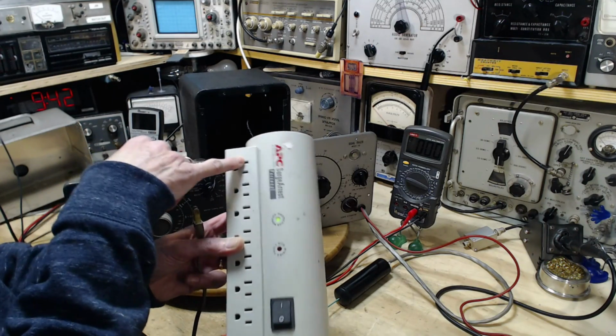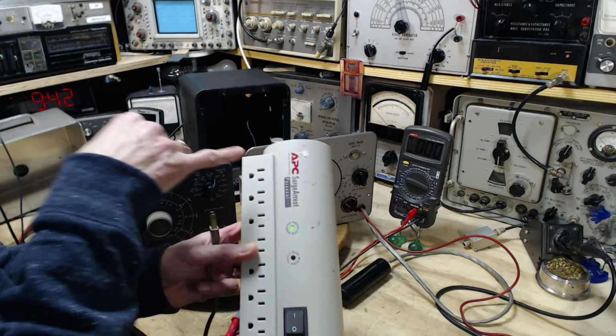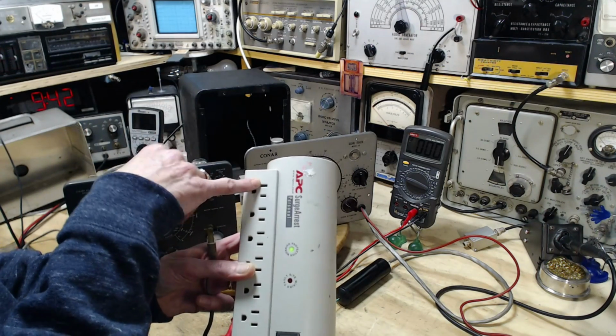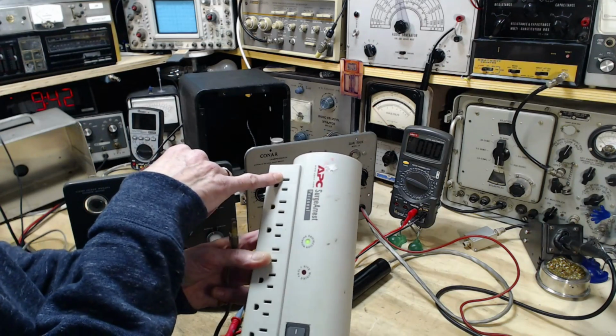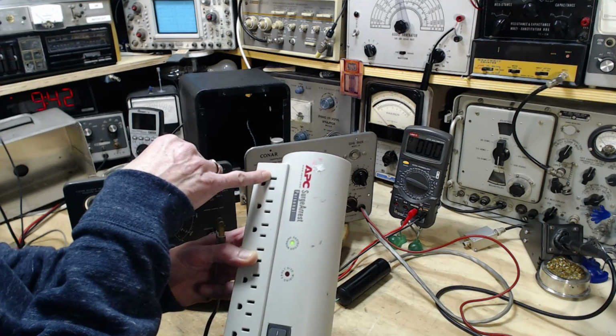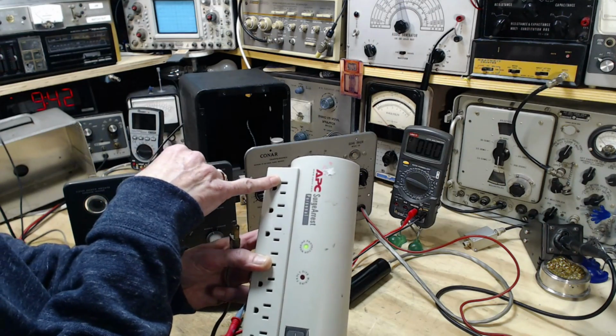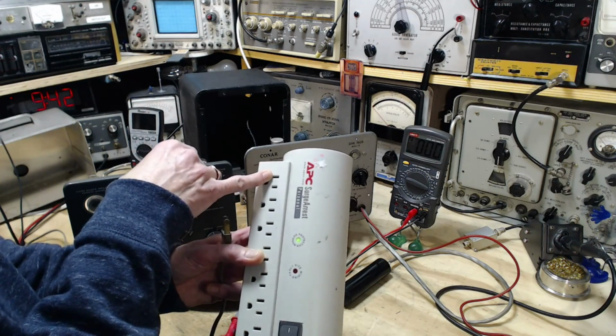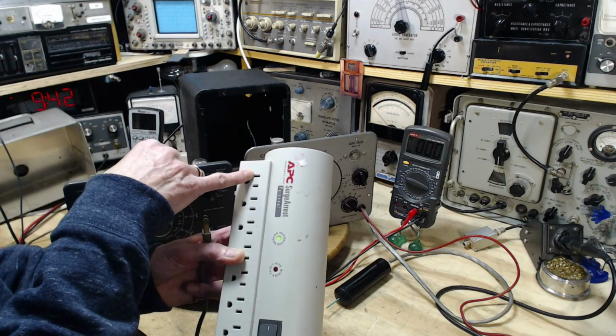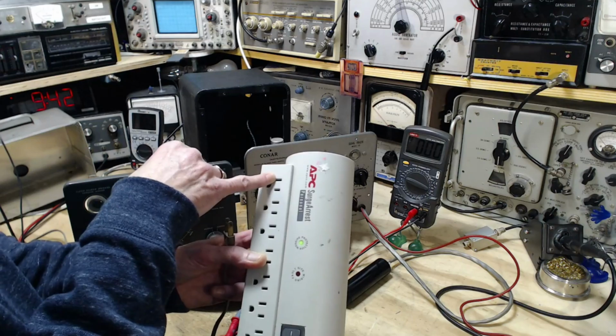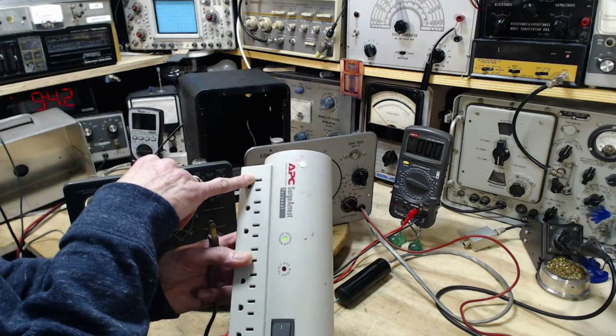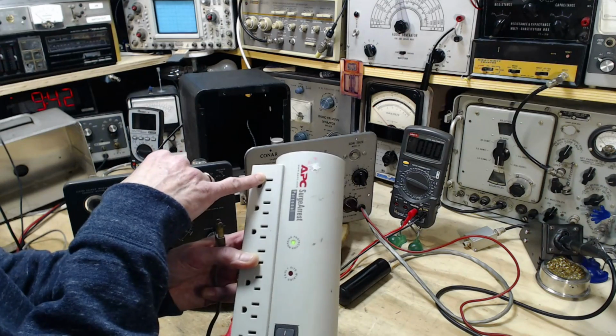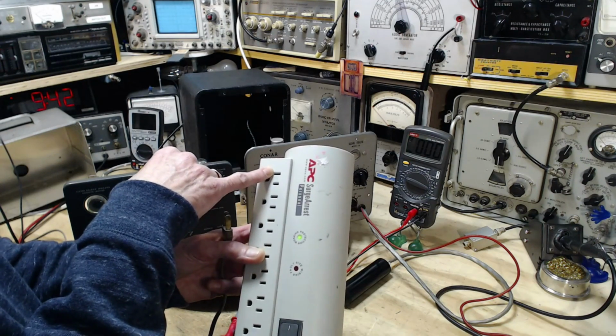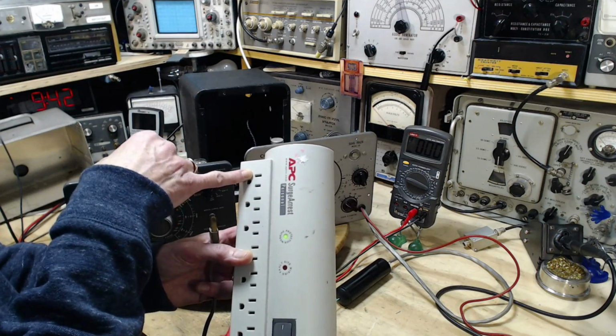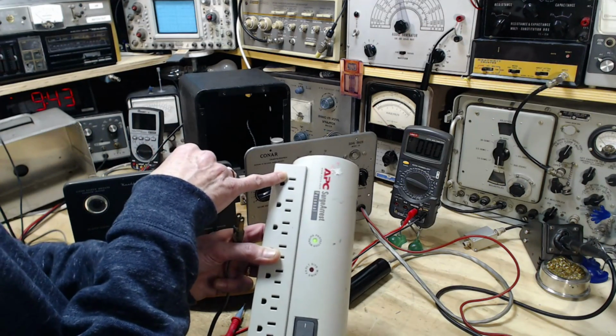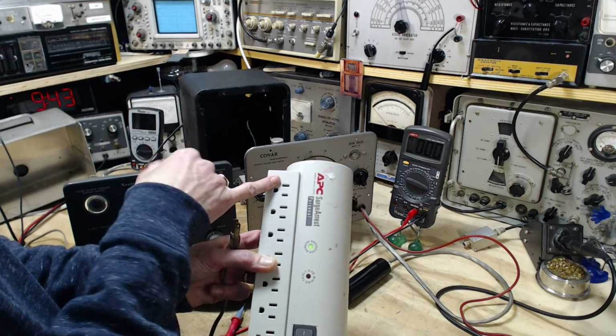Ground is a bad word to use, let me clarify the language here. This is the terminal that in my house leads to the wiring connected to the neutral coming into my house. The neutral is probably connected to a ground rod at the pole in my backyard. Normally a ground rod is placed at the base of poles that have transformers on them, for a couple of reasons, some of it being worker safety. So when I say grounded, that's how far it is to the ground rod from here.